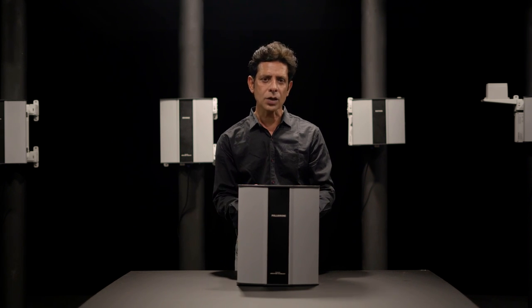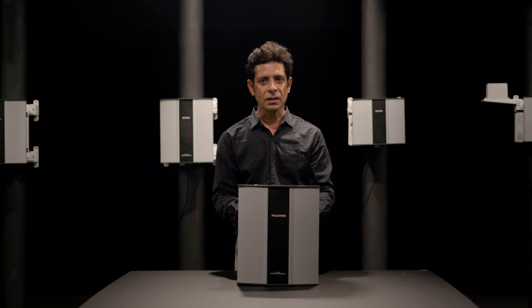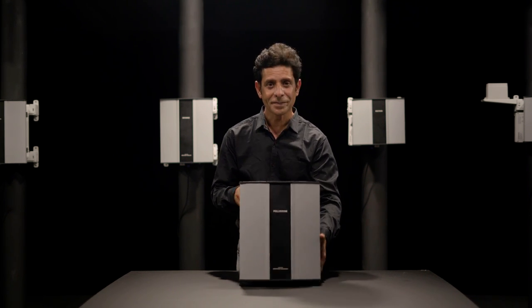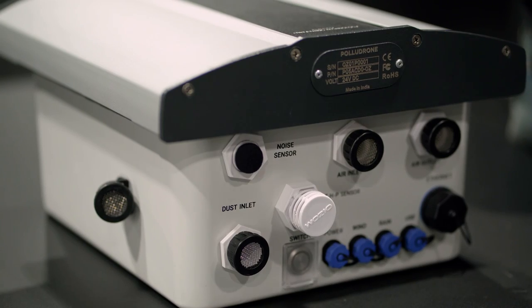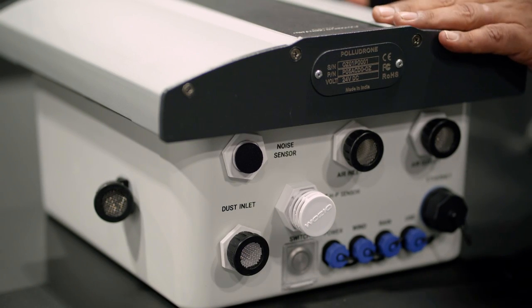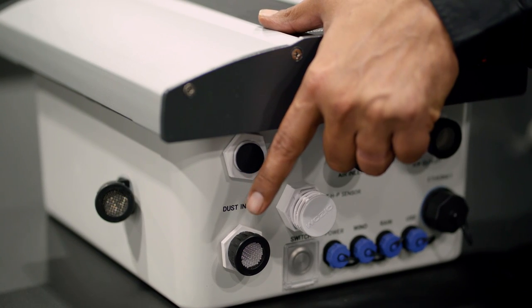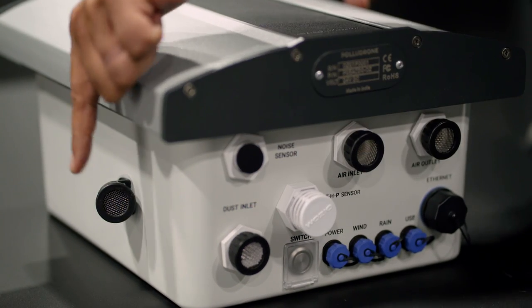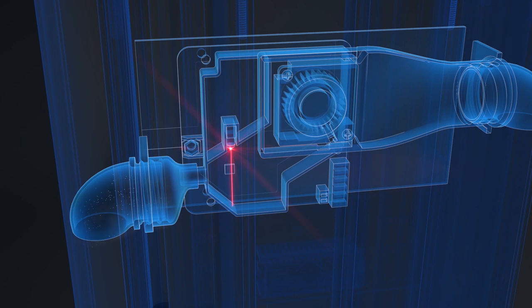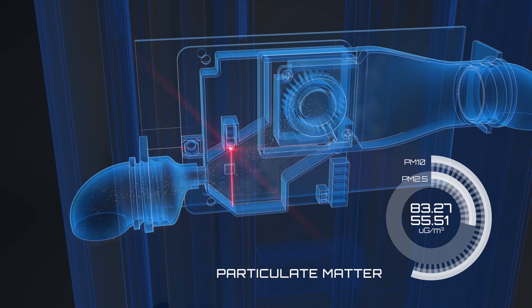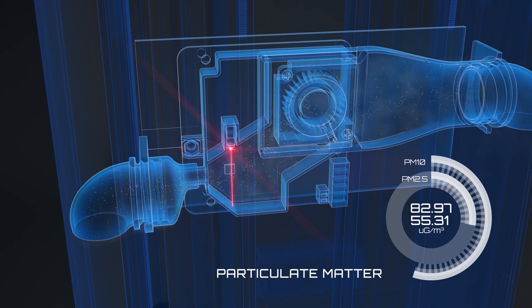To begin with, one of the most harmful pollutants is dust. To monitor dust concentration, the Polludrone operates on the principle of laser scattering. It is an active sampling method where constant air flow is passed through the system. The air sample enters through this inlet and exits from this outlet. Inside is a laser beam which continuously counts the particulate matter present in the air sample to derive the concentration of PM1, 2.5 and 10.